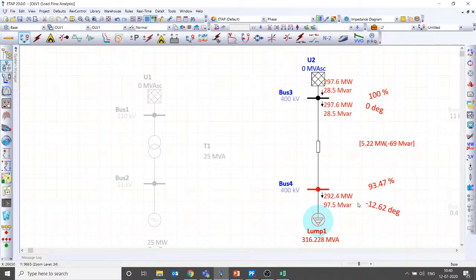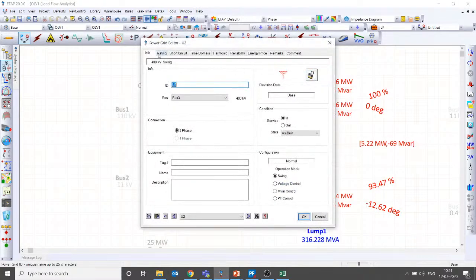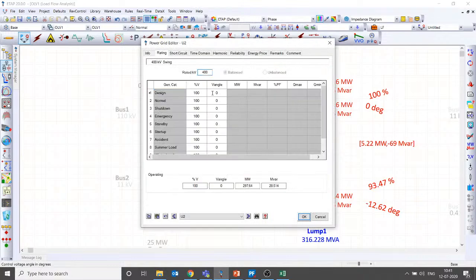In some of the previous classes we have discussed that real power flow is always from higher angle to lower angle. Here is the swing bus, and if you connect a load here, the power has to flow in this direction, so this angle has to be less than this. Since you have given 0 here, this will automatically be less, so it goes negative. If you assume the slack bus angle is 30 degrees, then 30 degrees minus 12.62 degrees will come at this place, which will be positive. But in reality, what we need to look into is the angle difference with respect to the reference angle.